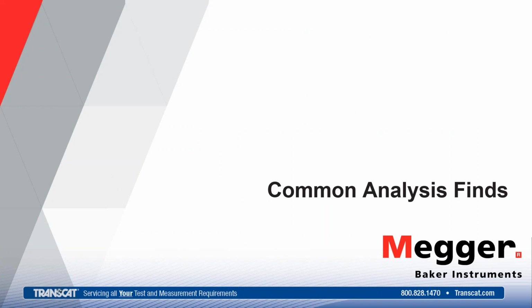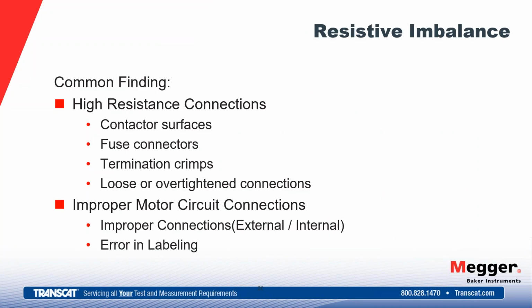So common analysis of our faults, again, resistive imbalance. We're going to look at high resistive connections that can cause imbalanced voltage, imbalanced currents, higher heating in that motor. High resistive connections can be the contactor surfaces, fuse connectors, termination crimps, loose or over-tightened connections. A lot of times if you're testing switchgear, you get a resistive imbalance, you open up the junction box and water pours out to your feet. That's an indication that you may need to revisit those connections.